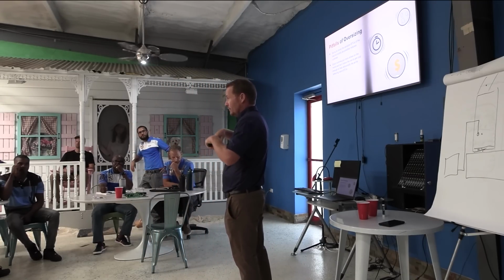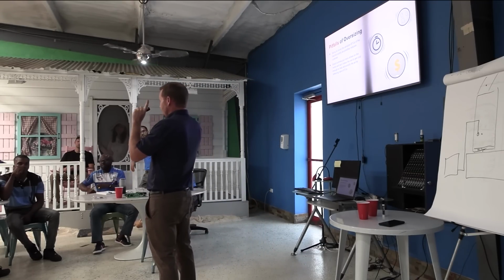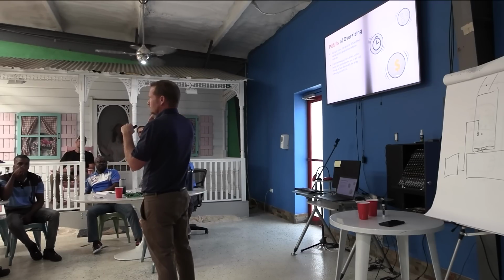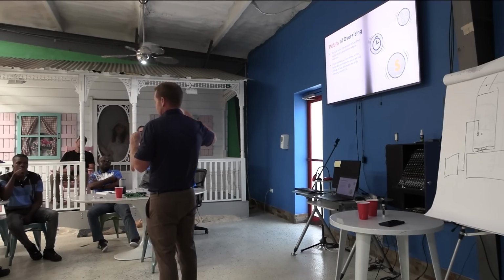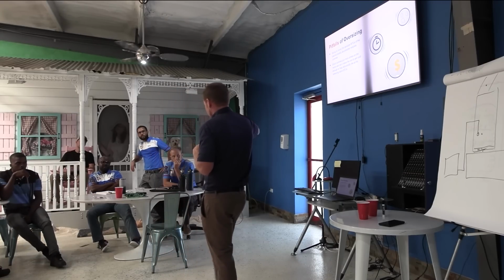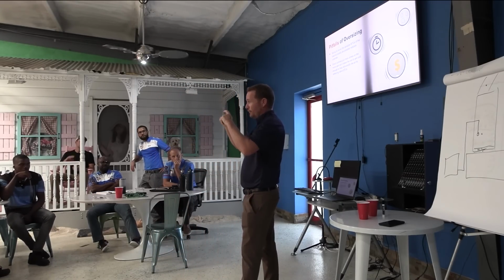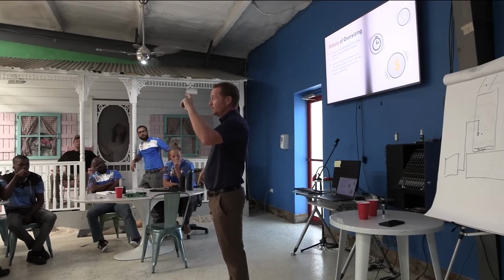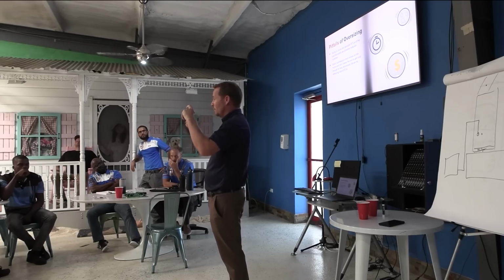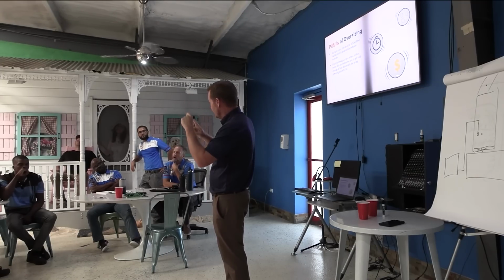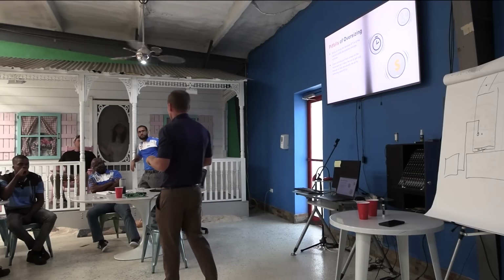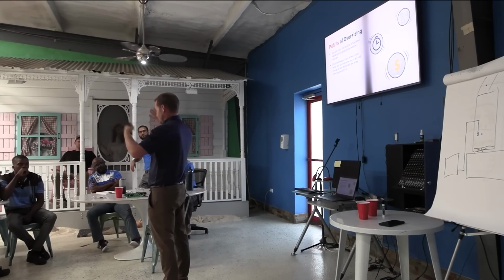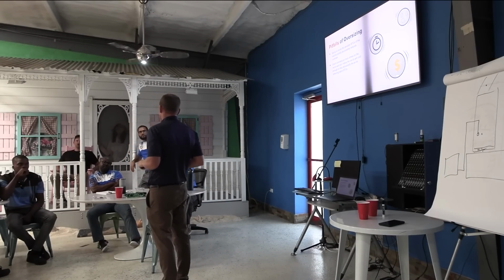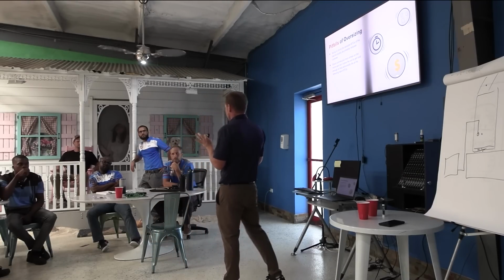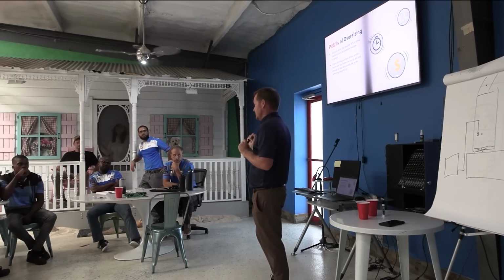In your market, for those of you designing, you want lower sensible heat ratios, SHRs. That means of the fraction of one that is sensible heat, you want less of that, and more latent, because a lower sensible heat ratio means a greater latent heat ratio. So when you're looking at charts, doing expanded performance data, and picking equipment, which is among the most important things you can do in sales, pick things with a low SHR.